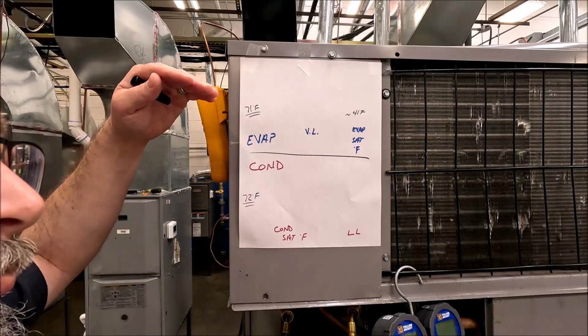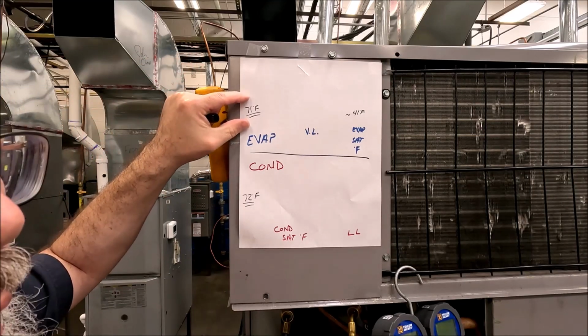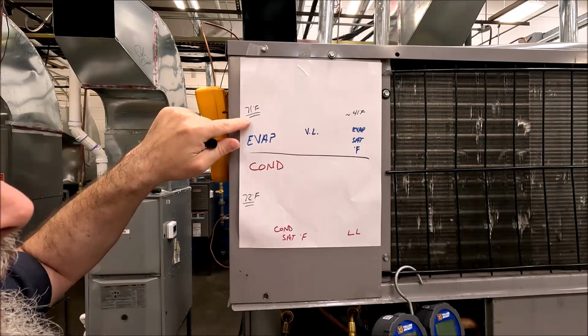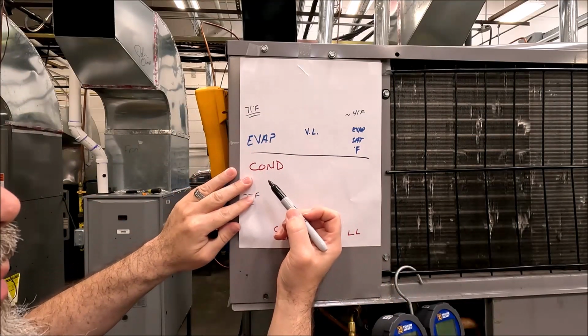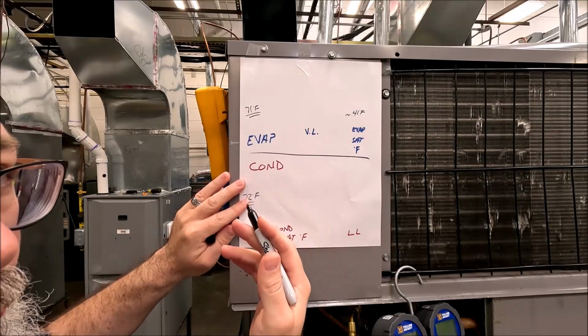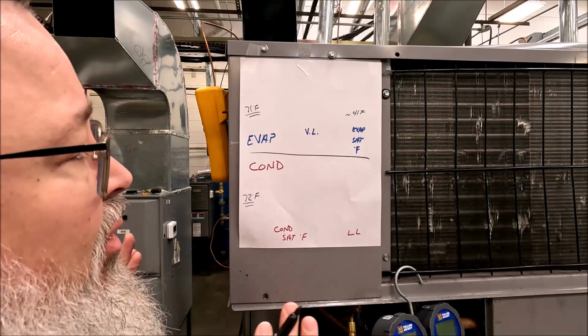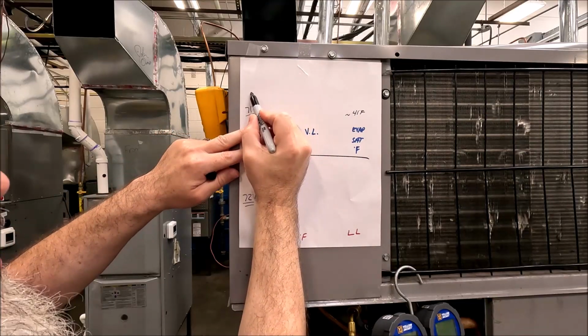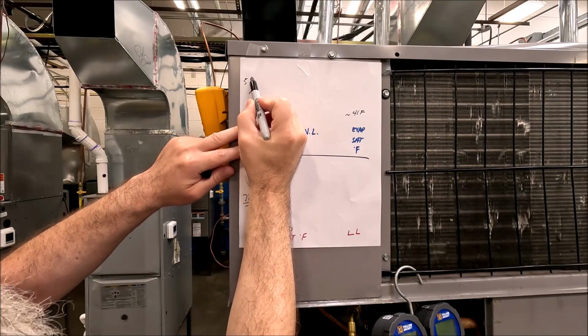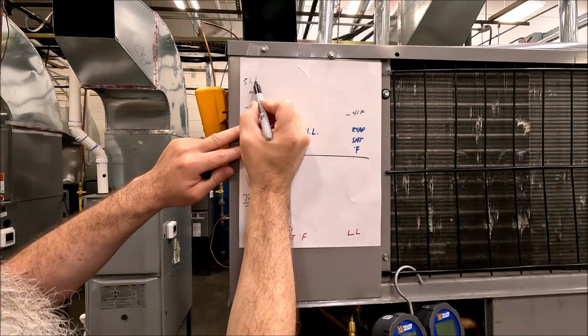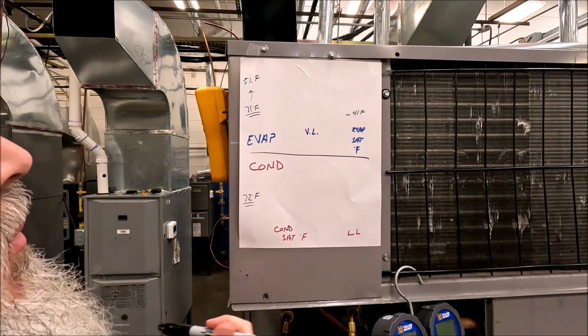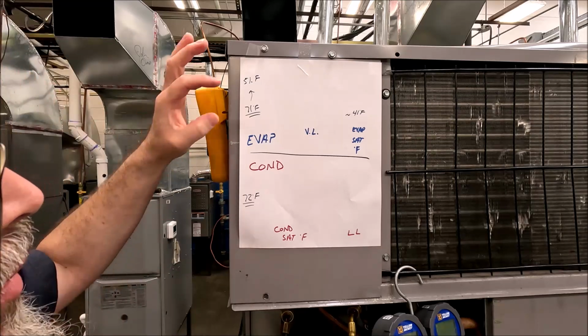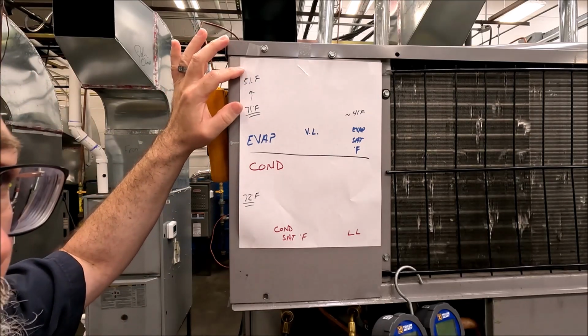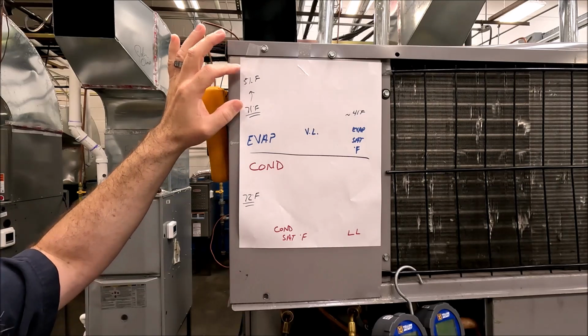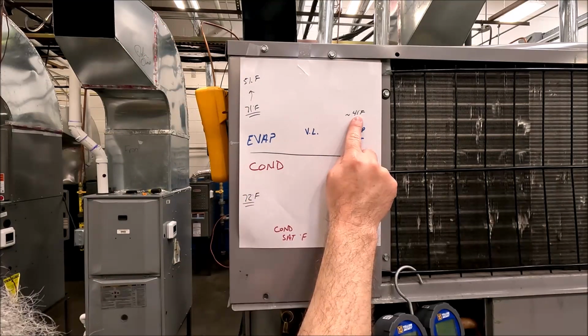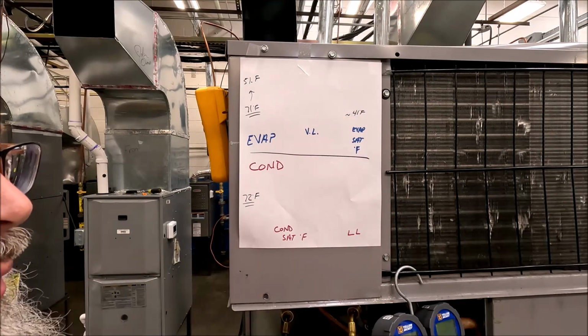Using the other low side rule of thumb, the one that involves the air temperature, if this unit is on point for proper charge and airflow, which we're not getting into, we're assuming is perfect, that temperature ought to be somewhere around 51 degrees. So if I got about an 18 to 20 degree drop in my air temperature over that evaporator, I'd be happy, okay? If I got a 41 degree saturation point on this evaporator, I'd be happy.